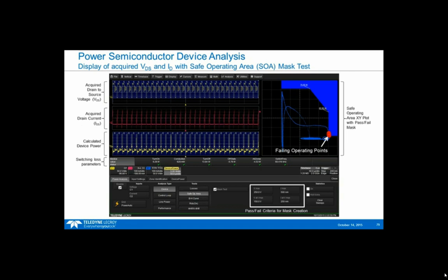I can do this over very long acquisitions. Now this is showing multiple zones with multiple calculations, with a mean value here in this table. There's also a safe operating area plot you can do, where you can apply a mask. This is the XY plot of the safe operating area, and here are the failing points where it's just a little bit outside of the safe operating area for the device.